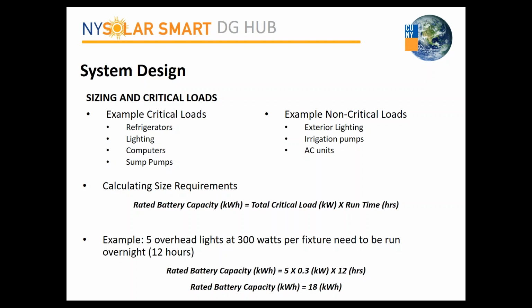We've laid out a really simple equation to calculate what battery capacity would be required for different system configurations: critical load times runtime gives you the rated battery capacity. A simple example: if a site has 5 overhead lights, each 300 watts, and the lights need to run overnight, you multiply those 3 numbers - 5 times 0.3 kW per fixture times 12 hours - gives you 18 kilowatt hours of battery storage required.